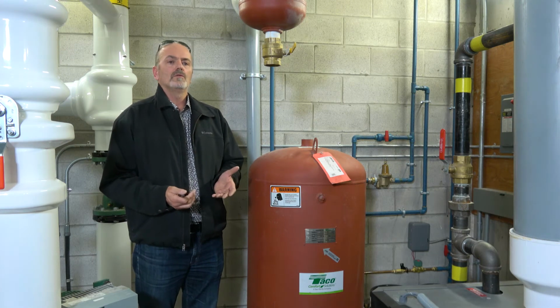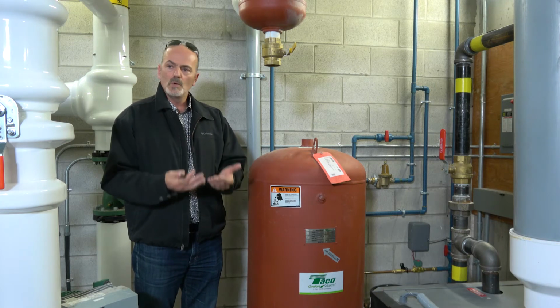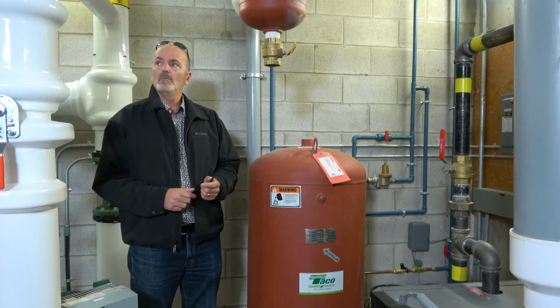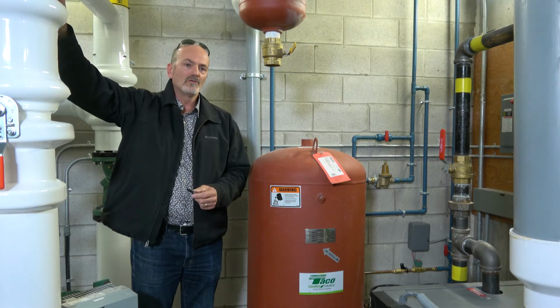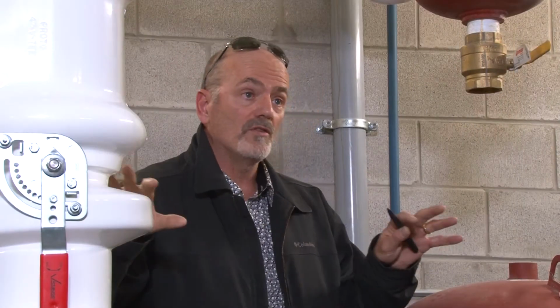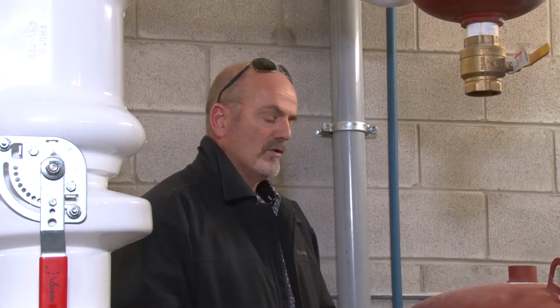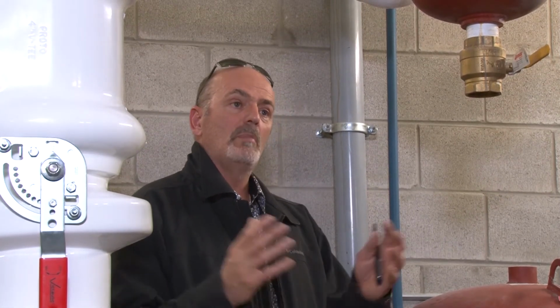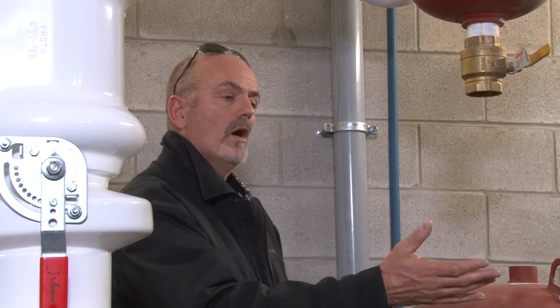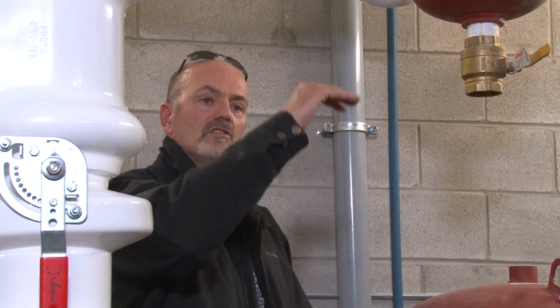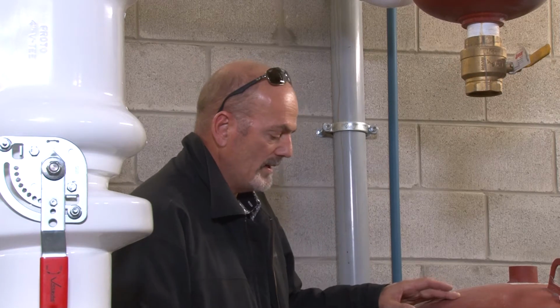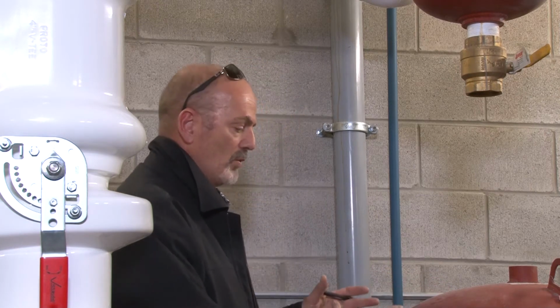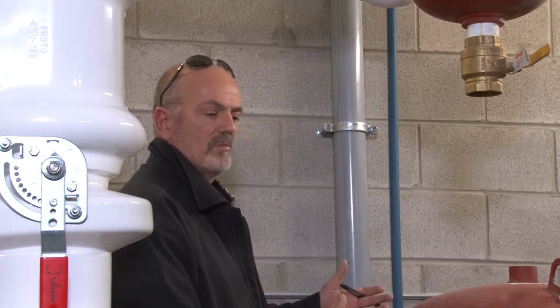as system fluid temperatures go up and go down in an enclosed system. What I mean by enclosed is it's all in piping, there's nowhere for it to go. Water and or glycol water tend to expand and contract. So if it expands, you need a place for it to go. So as you heat the water and the boilers are running and you bring the system temperature up, the water will expand.